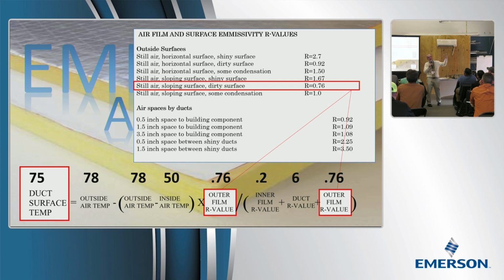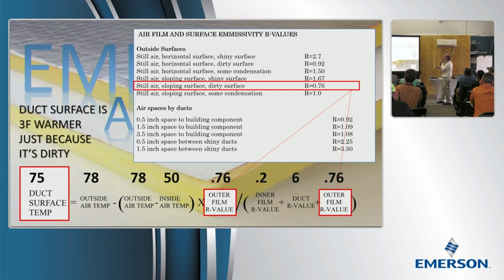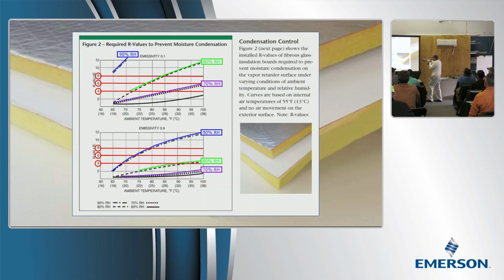So you can buy the ducts already dirty. You don't have to pay employees to get the ducts dirty, but it is true. Dirty, opaque stuff that's not shiny doesn't sweat nearly as much. If you notice, 3 degrees is more than you got out of raising your supply air temperature. You only got 1 degree out of that. When you went from R6 insulation to R8, you only got 2 degrees. I got 3 degrees just from getting it dirty. I can do that, and I can buy it already dirty.